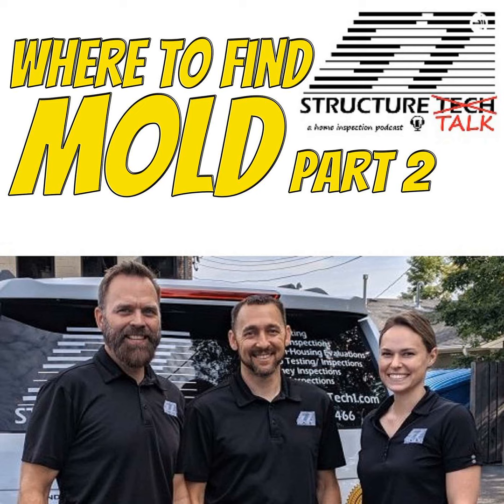Anytime you run ductwork outside the thermal boundary of the house, outside the insulation, you're taking conditioned air - like cold air in summertime - through that ductwork in a hot attic, and you're more likely to get condensation forming on the duct. Then you get issues with condensation and moisture, not to mention energy efficiency problems from losing cooling. In wintertime it's the opposite problem - you're losing heat into the attic space, which can create ice dam issues. And if you've got leaky ductwork, you're pumping warm, moist air into the attic, which creates problems in and of itself. Running ductwork through an unconditioned space like that increases the potential for condensation, energy efficiency problems, and building performance issues. So I always prefer ductwork inside the conditioned space - not in the slab, not in the attic, not in a tuck-under garage ceiling, but in the house.